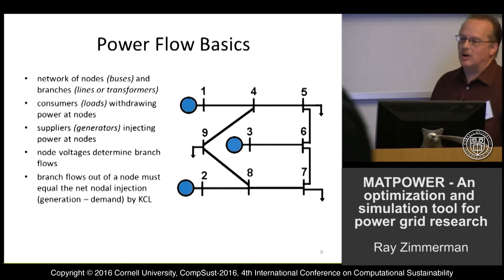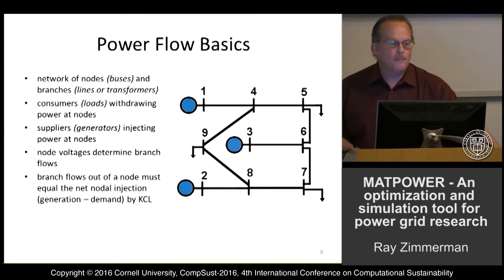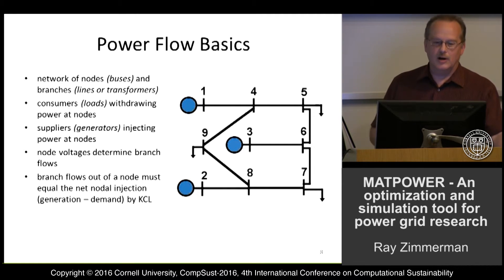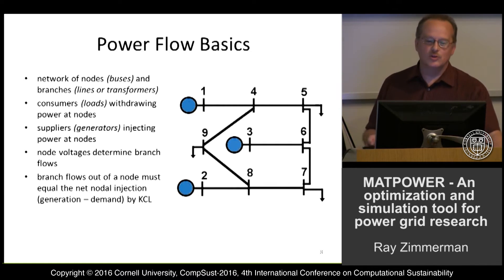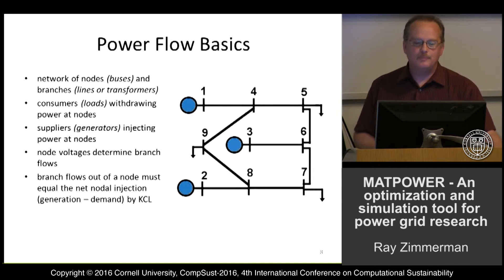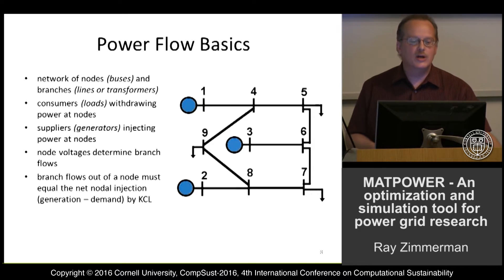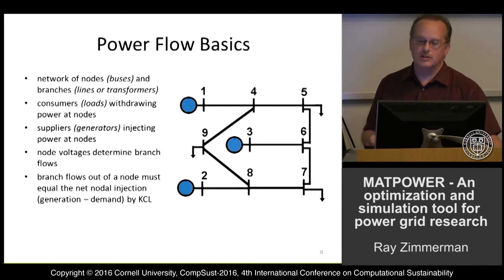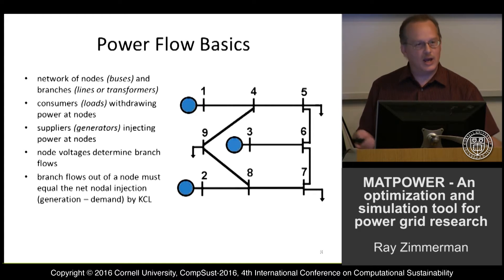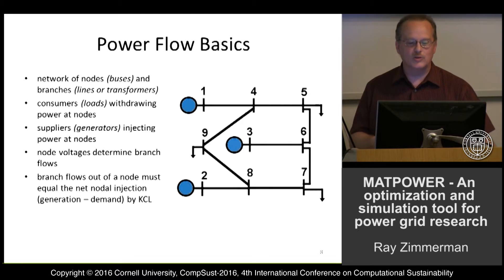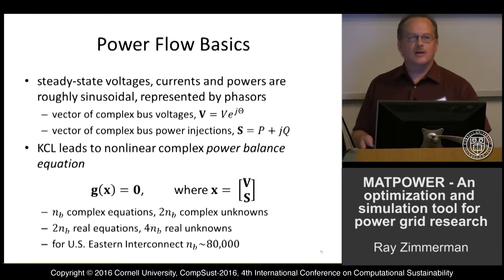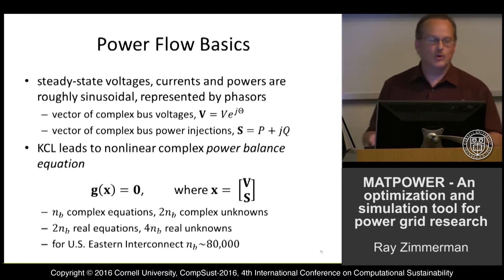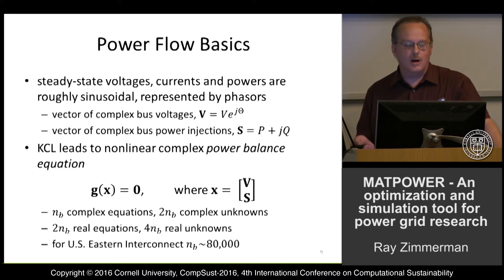Starting with Power Flow and Continuation Power Flow: in the power flow problem you have a network of nodes, called buses, and branches connecting them — transmission lines or transformers. Consumers or loads withdraw power at certain nodes, suppliers or generators inject power at others, and node voltages determine the flows in the branches. Kirchhoff's current law says flows out of a node on the branches must equal the net injection — generation minus demand. The steady state voltages, currents, and powers are roughly sinusoidal, so we represent them by phasors, which are complex numbers.